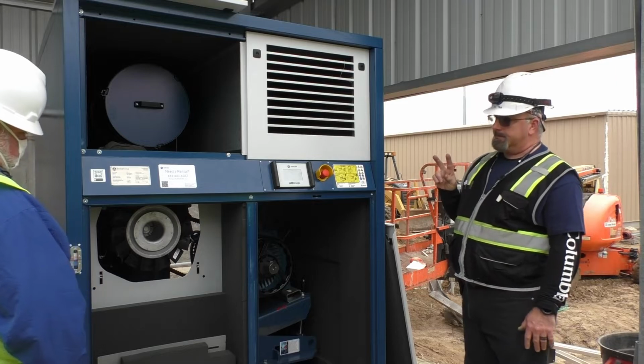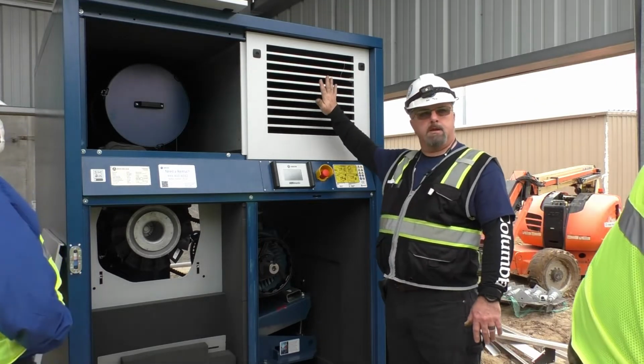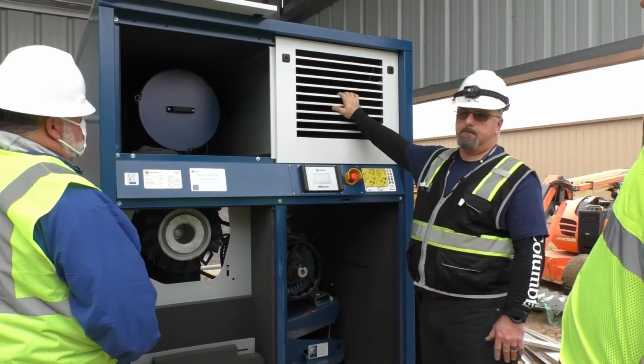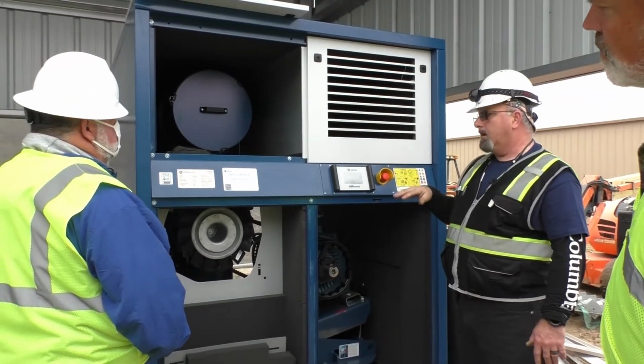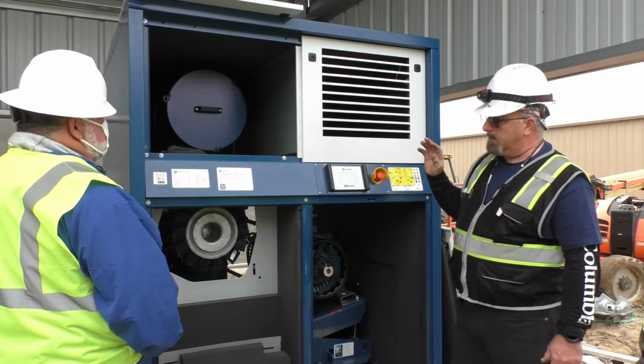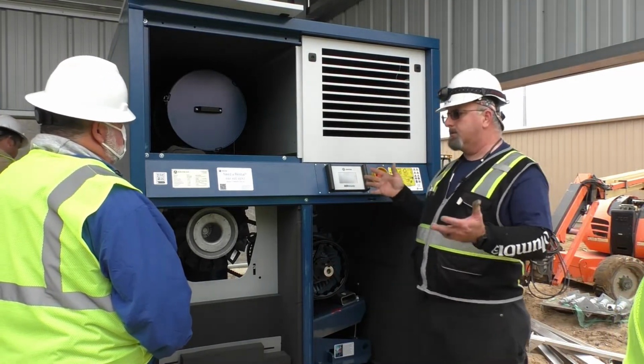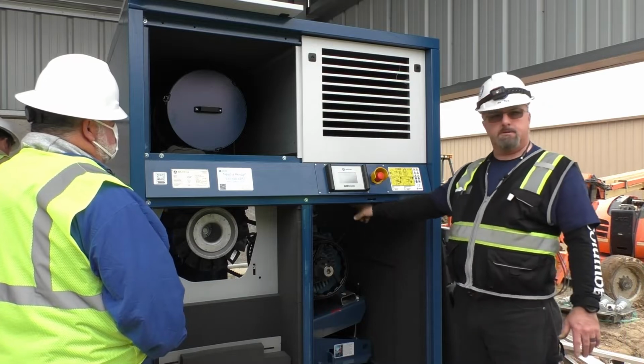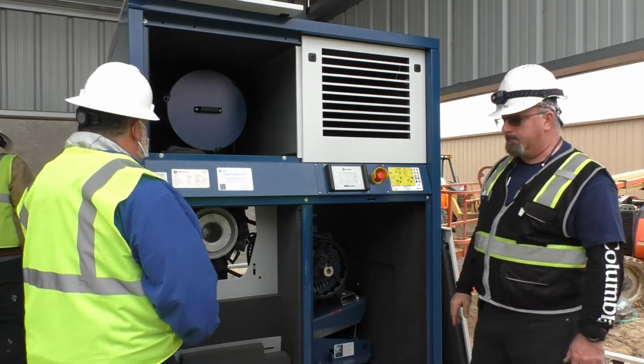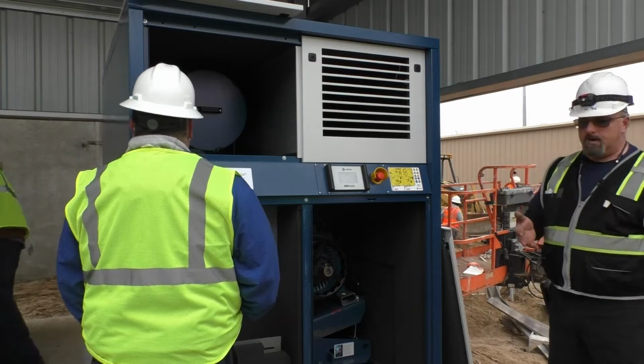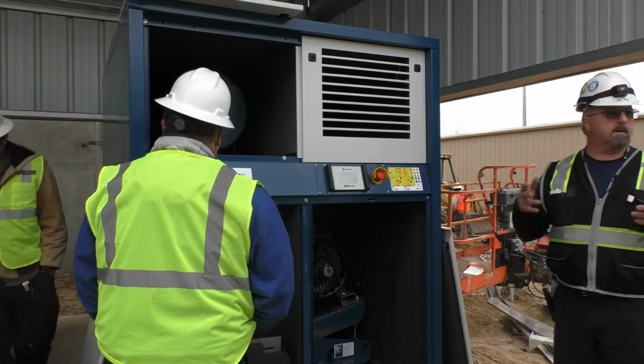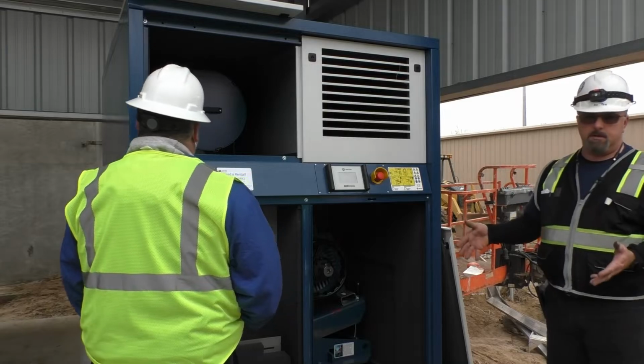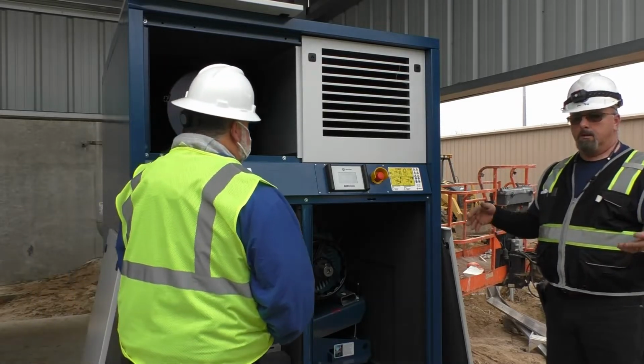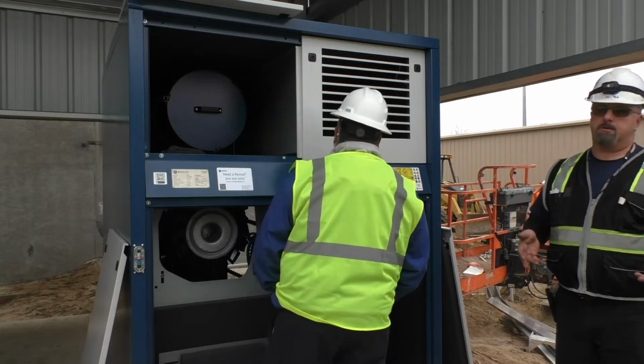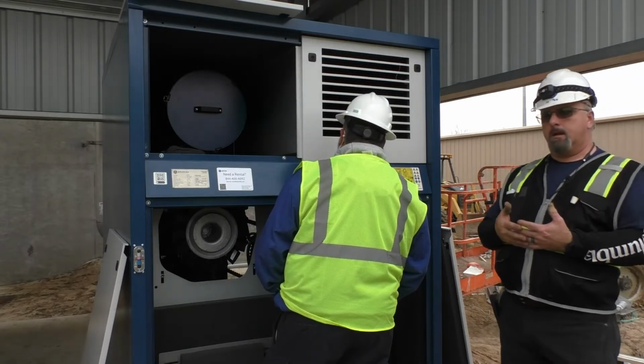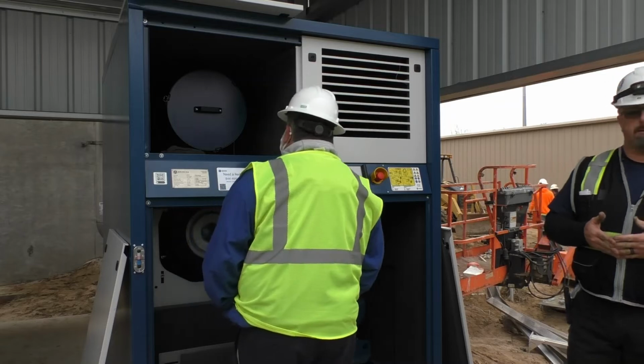It does that for two reasons. Number one, this way you're always pulling in cooler air than you're exhausting out. If you ever reach a point where you start running a higher temperature than what you were, you may want to make sure that your exhaust back there at the back is not clogged by rats building a nest under there, raccoons, that type of thing, because you can't restrict it. You could put a screen up to prevent rodents from getting in there, but you'd have to make sure you cleaned it. That would add an additional service item you would have to look at.